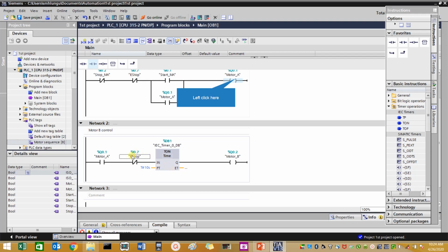So I'm just putting in this e-stop, but in fact I don't even need it, because this motor depends on this timer, and there's a dependence again that says this timer will never run unless this motor is energized. But I'm just putting it there for safety purposes. I hope it's fine with you, because it depends on this contact. As long as this contact is open, this timer will never count, and it will never time, and at the same time this motor will never run. I hope you guys are happy with that.